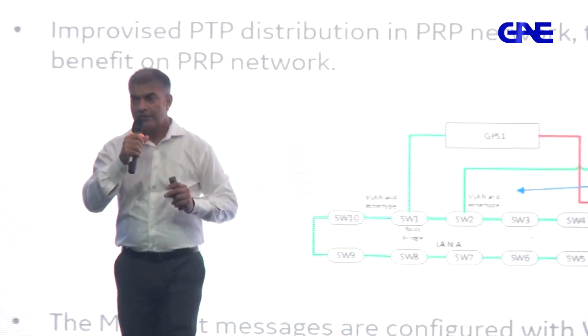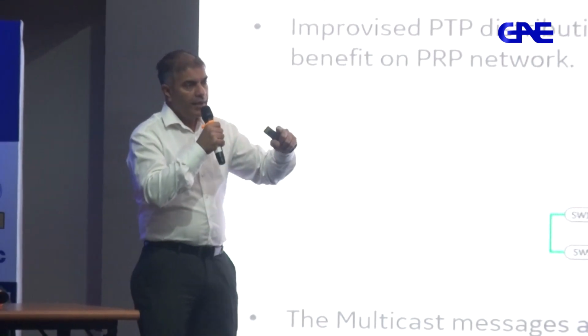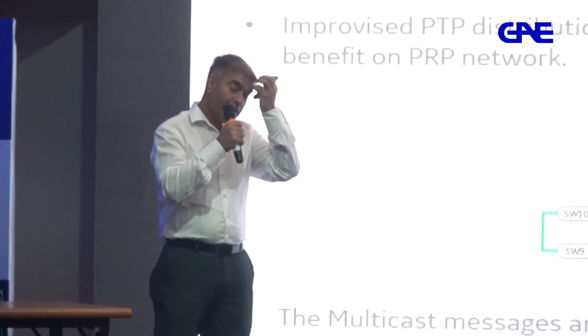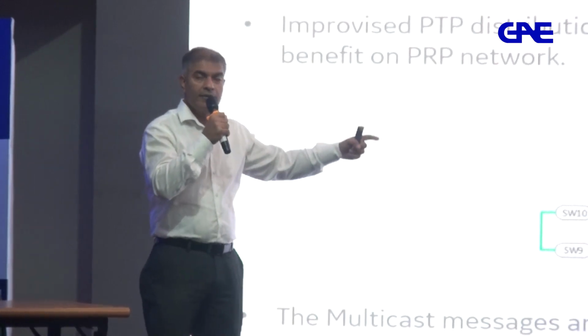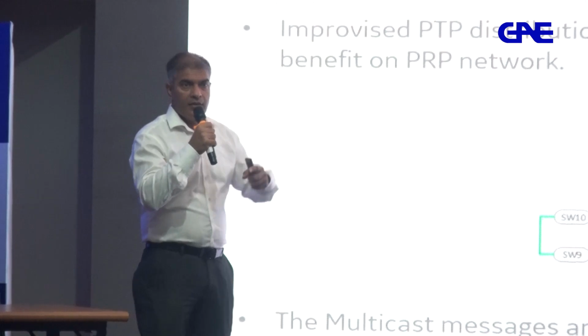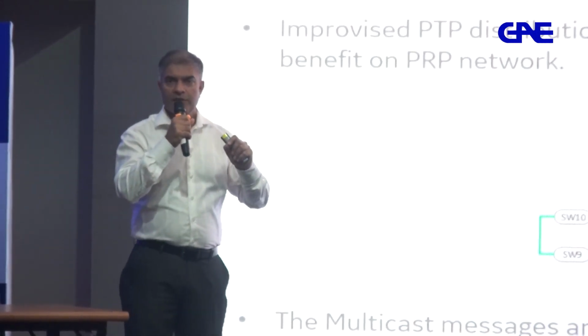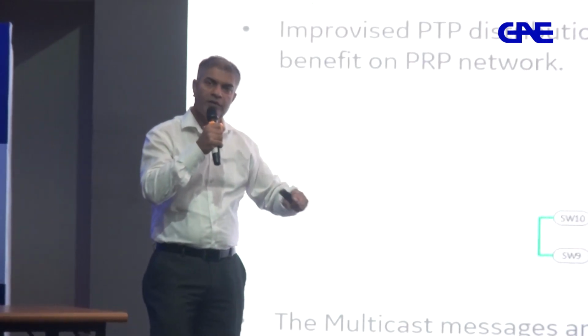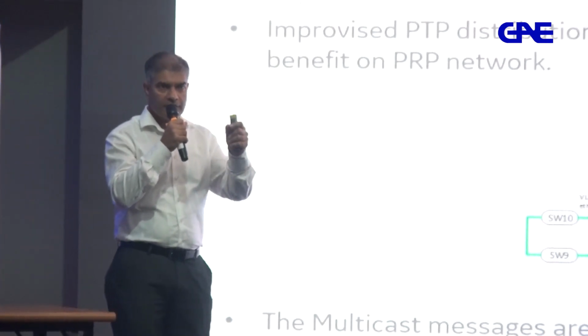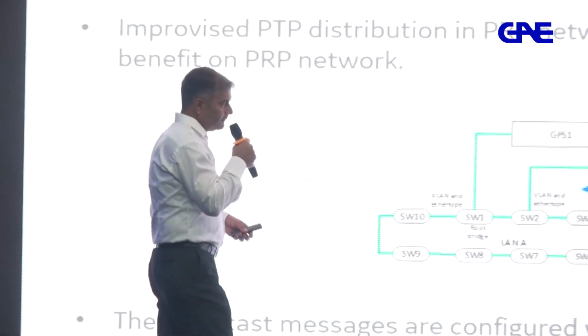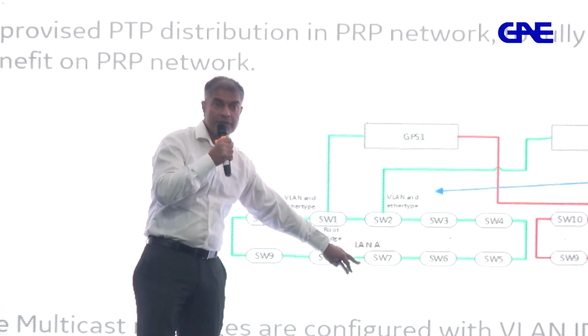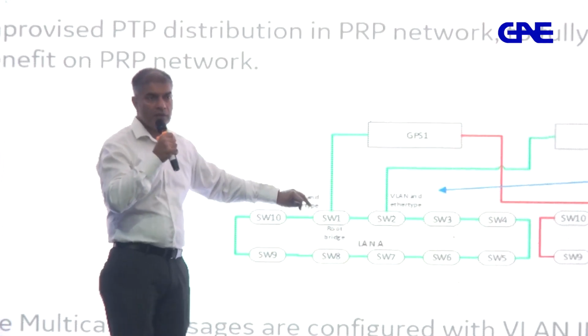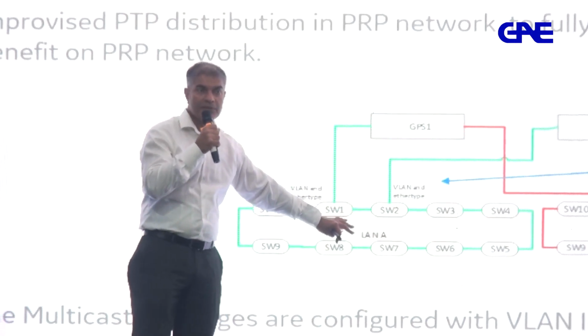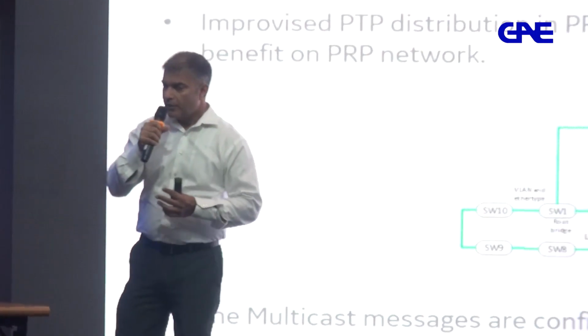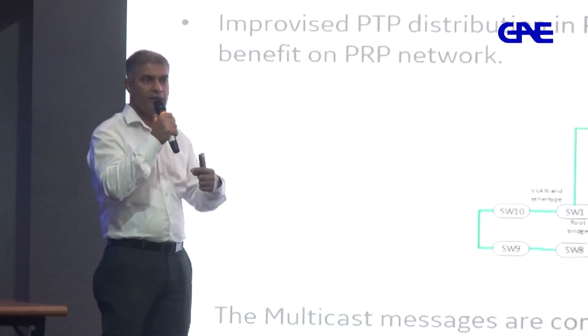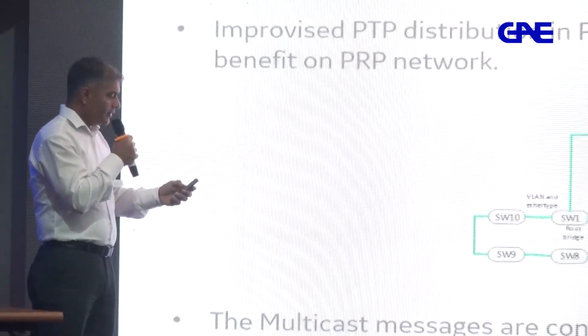Effectively, when you have PTP and your network is very big, in some of the substations I have seen that the switch network has about 20 to 25 switches, right? For PTP, if you want to maintain accuracy of 1 microsecond, the message should not travel more than 16 switches, because at every switch you have loss of accuracy, right? So here what we have done is that you have one connection here and one connection at the opposite end. So if any switch fails or any clock fails, you have an alternate message available at one of the ends. That means in any contingency, your PTP message will not need to travel more than 16 hops. So that's just one design we did.